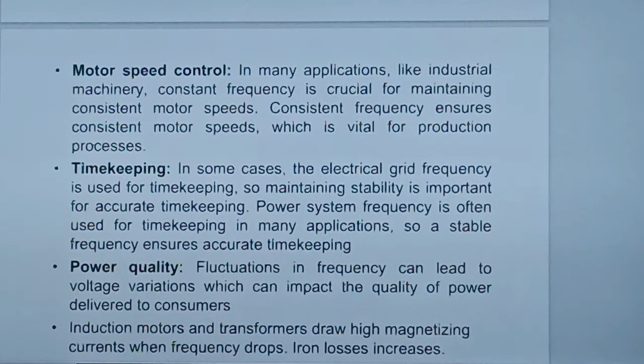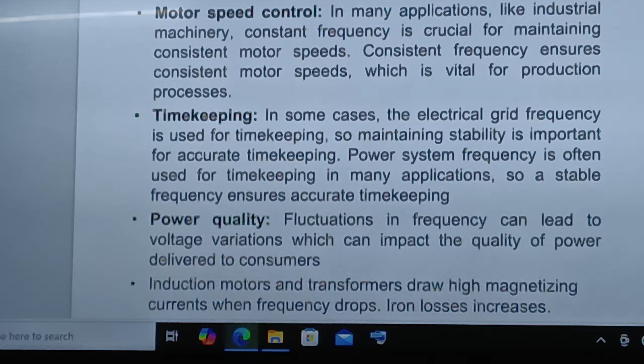So we have studied fundamentals. For example, the transformer: there are iron losses, again hysteresis loss and eddy current loss. They depend on B maximum, the maximum value of flux density, which is given by the V by F ratio. V is the applied voltage, generally maintained constant. So if you change the frequency, that B maximum value will change, so the losses will change. If more loss occurs, it will obviously produce more heat, and the life period of the equipment will decrease.